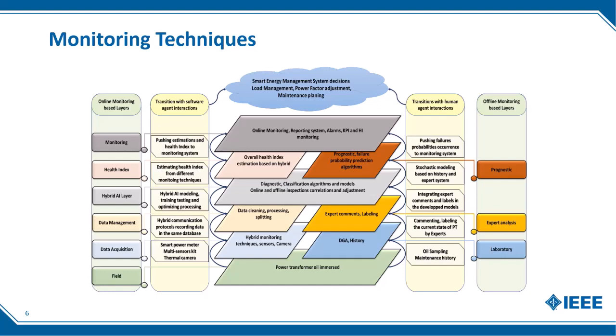There is also thermal imaging, using a thermal camera to detect hotspots on the surface. There is vibration analysis, which involves measuring vibration in the transformer, and noise analysis of sounds emitted by the transformer, analyzing the data to detect potential issues. There is also ultrasonic testing, visual inspections to identify visible signs of damage or wear, and calculation of the overall health index.